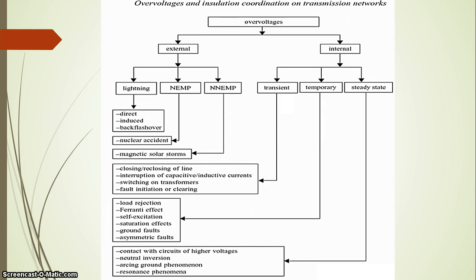Under internal overvoltage, transient overvoltages occur due to switching off capacitor banks, switching off transformers, closing and reclosing of lines, and fault initiation and clearing. Also, temporary overvoltages occur due to the Ferranti effect, where the receiving end voltage becomes higher than the sending end voltage during no-load or lightly loaded conditions, and due to load rejection.